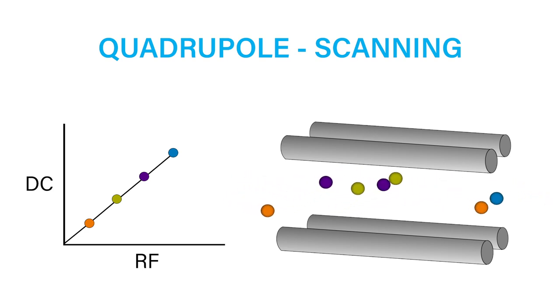The scan time is the amount of time the quadrupole spends scanning the entire mass range, from the start mass to the end mass.